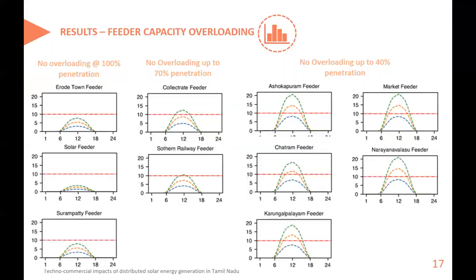In the first result analysis, you can see the feeder capacity overloading. As I said before, the maximum feeder power carrying capacity is calculated as 10 megawatt for all the feeders, and since the penetration level was fixed according to each feeder's annual energy consumption, the amount of solar capacity connected to each feeder will differ. So let us see which feeders can go up to 100% penetration level.